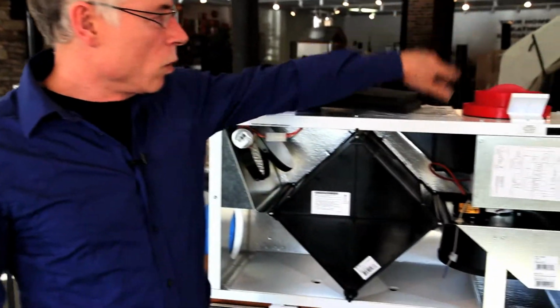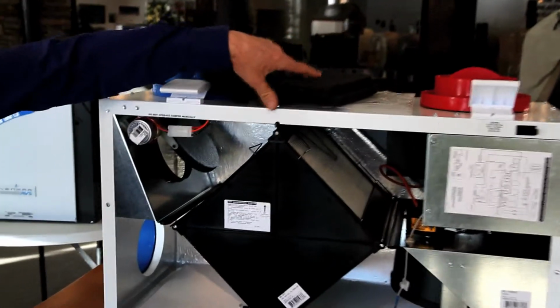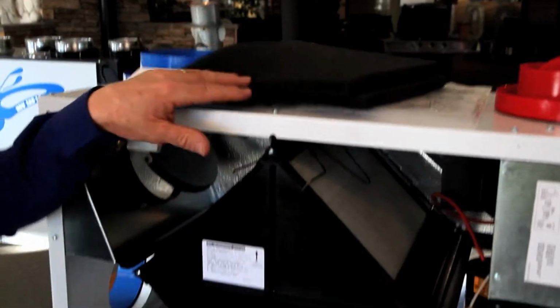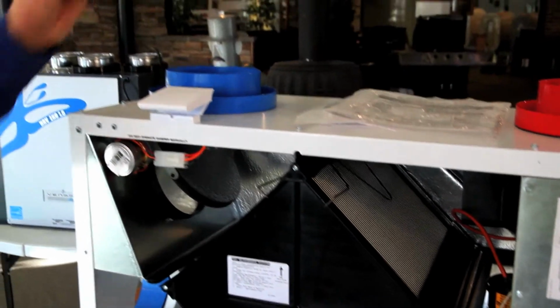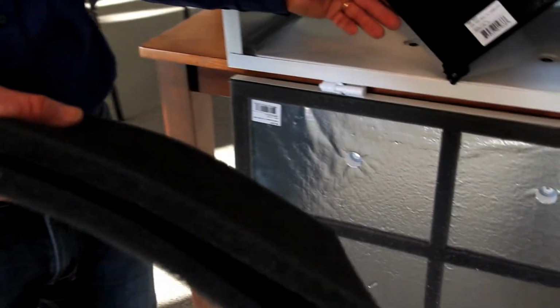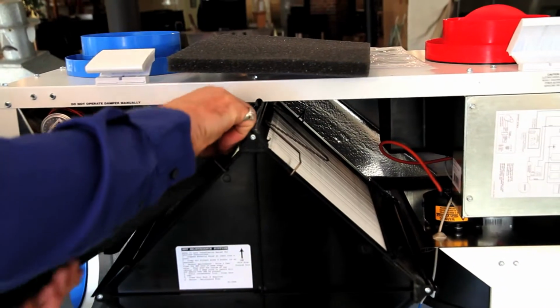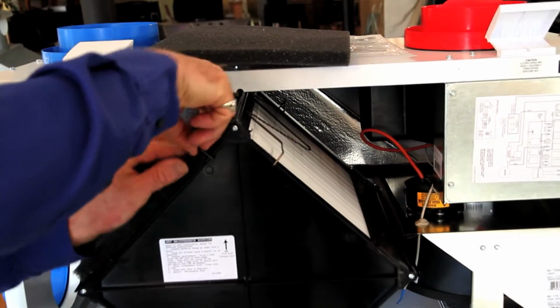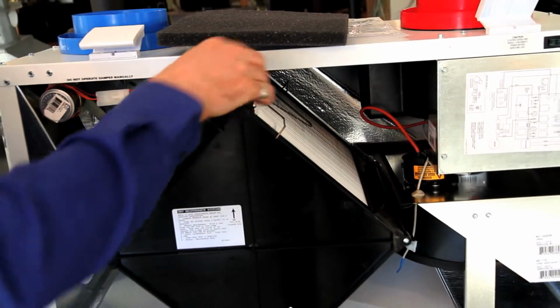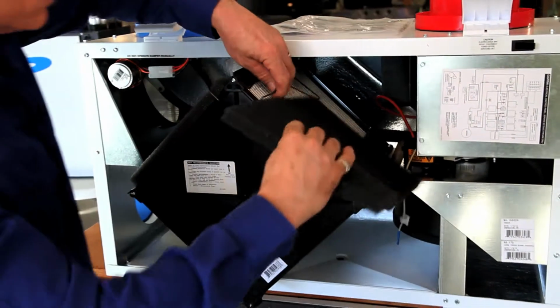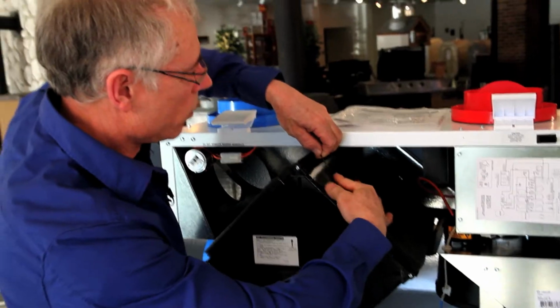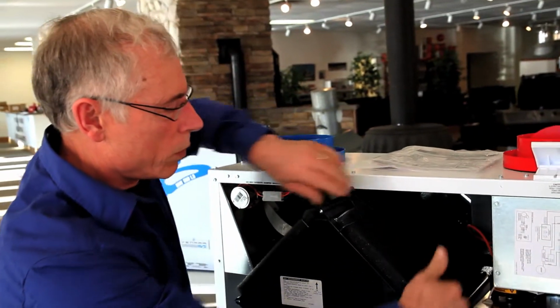The homeowner should familiarize themselves with the HRV. The owner's manual is the first place to start. The core and the filters need cleaning, the core annually or more often depending on the recommendation of the manufacturer. The filters, a good time is in the fall because you get leaves and bees, etc. in these filters, so they just wash out with soap and water.